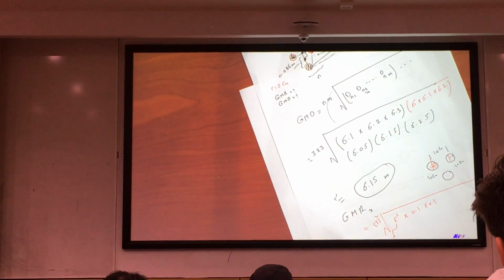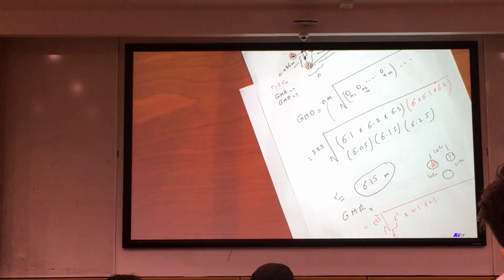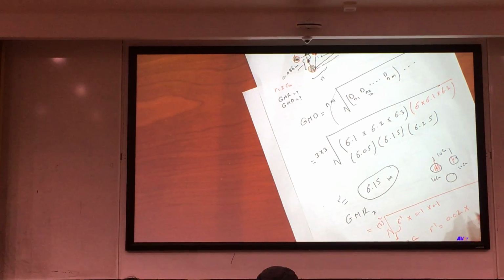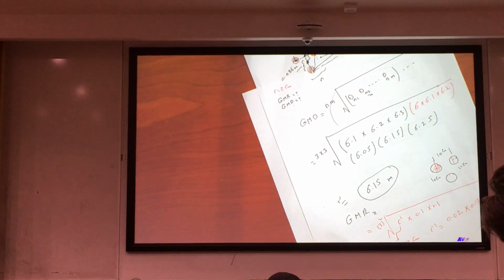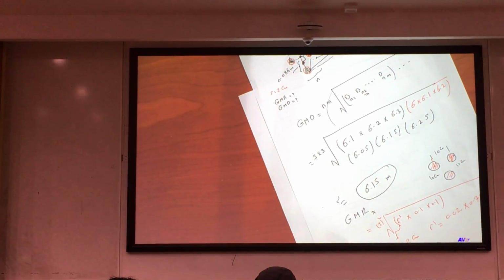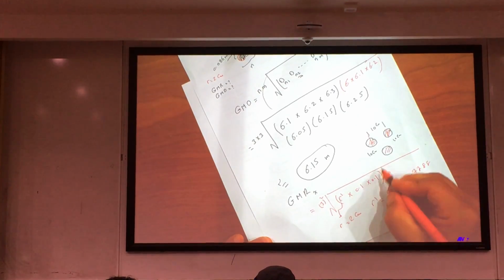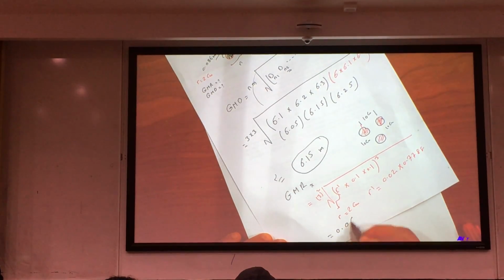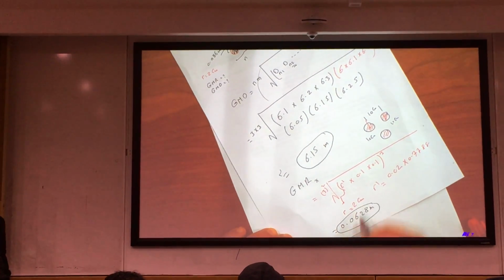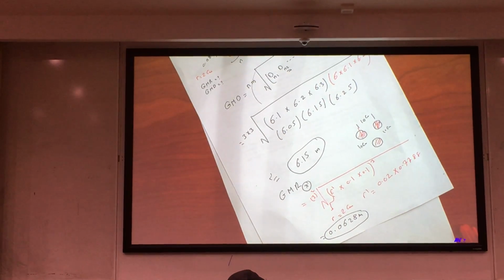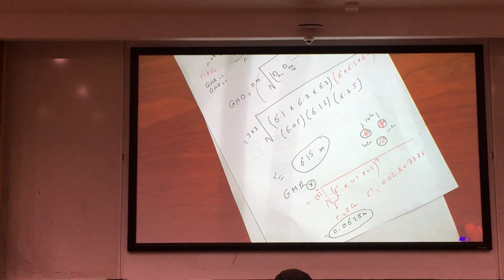Where r dash here is given to us. For this problem, r is equal to 2 centimeter. So r dash is equal to 0.02 in meter multiplied by 0.7788. I have to repeat this for conductor number 2 and conductor number 3, which will give me the same spacing, so I can write cube here, which can cancel the square. Then you will get your geometrical mean radius as 0.0628 meter. That's for x side, because in y side we have a different configuration and we will get a different geometrical mean radius.